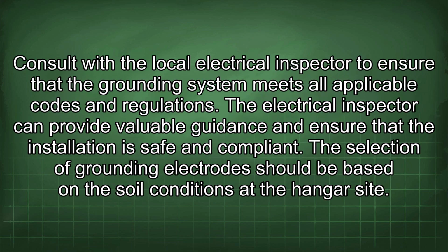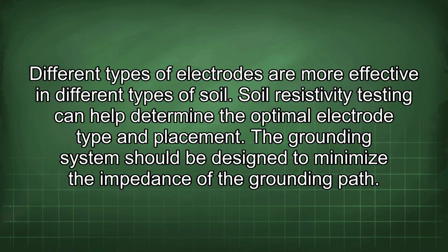Consult with the local electrical inspector to ensure that the grounding system meets all applicable codes and regulations. The electrical inspector can provide valuable guidance and ensure that the installation is safe and compliant. The selection of grounding electrodes should be based on the soil conditions at the hangar site. Different types of electrodes are more effective in different types of soil. Soil resistivity testing can help determine the optimal electrode type and placement.